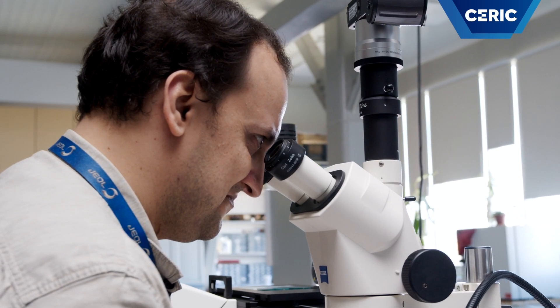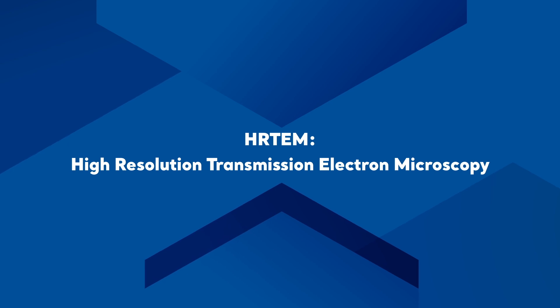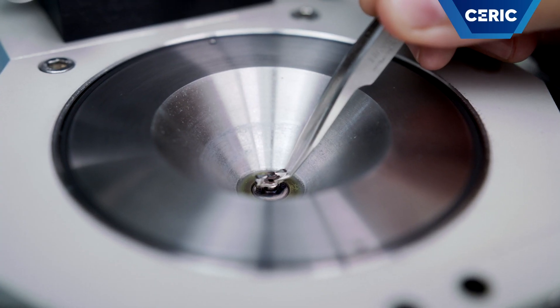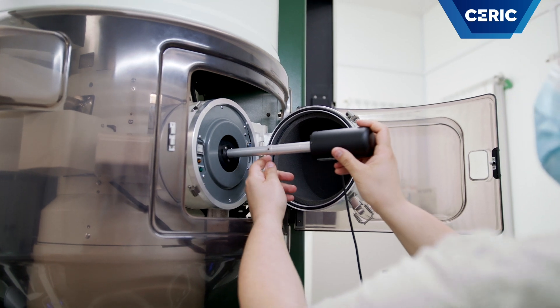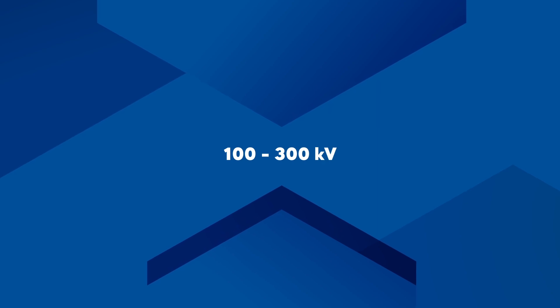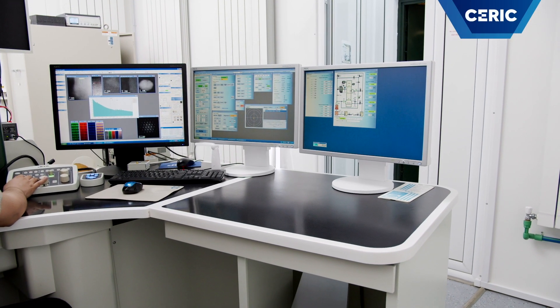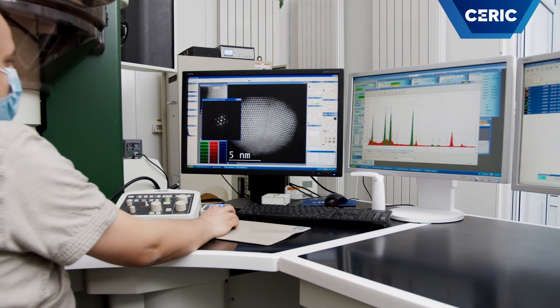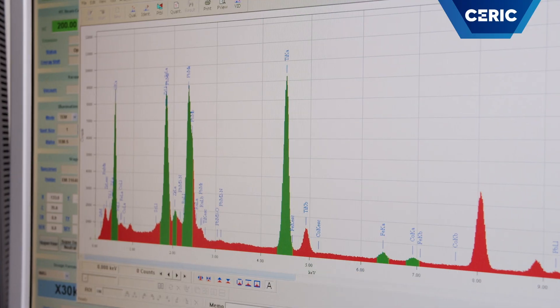High-resolution transmission electron microscopy, or HR-TEM, is a TEM working mode meant to visualize the atomic structure of crystalline materials. The thin sample is inserted in the way of the electrons accelerated by a high voltage, typically between 100 and 300 kilovolt. Electrons emerging from the sample carry information regarding elastic and inelastic atomic interactions experienced while passing through the sample, and can be used to generate enlarged images of the internal structure of the samples, electron diffraction patterns, or spectra revealing the local chemical composition of the sample.